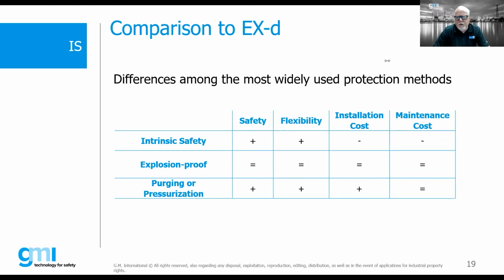Now, explosion-proof or flame-proof, from a safety standpoint, there are some potential negatives. Obviously, bolts being left out, corrosion, those are all different kinds of issues. Certainly, it has some flexibility, we can do a lot of different things with explosion-proof or flame-proof. As for ease of maintenance, now all of a sudden we have to open up these enclosures and do all this, we have to do lockout, tagout, and then certainly purging and pressurizing.